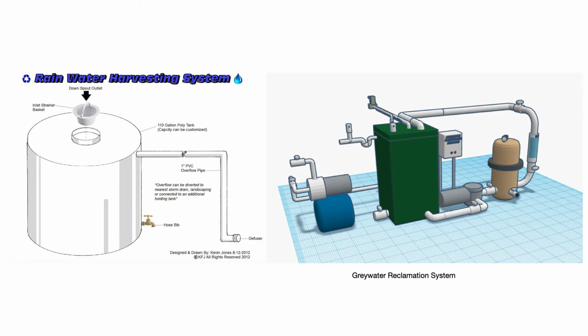Another option is a gray water reclamation system, as I mentioned earlier. Basically, the way that system works, the gray water enters into that green surge tank and is kidney looped, or basically filtered over and over again, through a diatomaceous earth pleated cartridge style filter that is reusable. And then the gray water passes through a UV sterilizer back into that green tank. So that's what kidney looping means. It just continually gets filtered. Then the water, once it's been cleaned and sanitized, goes to a pressure pump with a bladder tank. That pump is what would pump the treated gray water to whatever you need it for: to refill mop buckets, scrubber carts, to wash your floors, water cooling tower makeup water, etc. And there would be a final granular activated carbon polish filter just to make sure the water is nice and clean before it goes to the end user again.